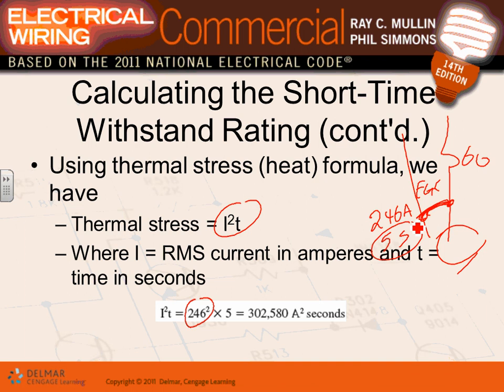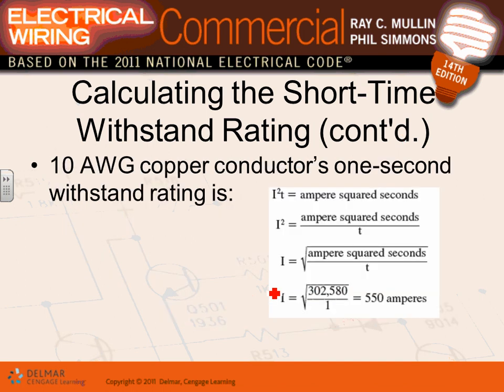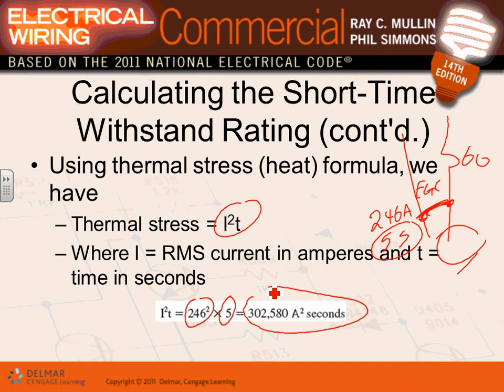So you take the current, you square it, multiply it by the 5 seconds. Gentlemen, this is the I squared T that you get. This is the amount of energy that this conductor will encounter under these circumstances. Take the current, square it, multiply by how much time you want it to stand. Typically 5 seconds. If I say 4 seconds, multiply by 4. Nothing really into it.